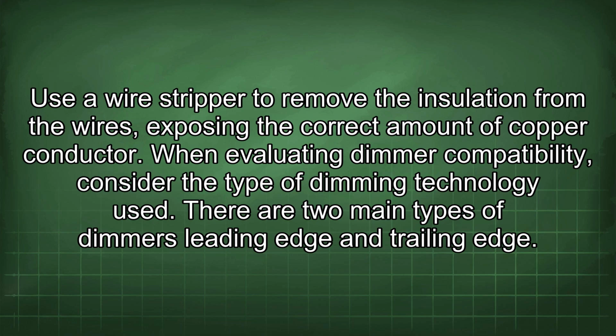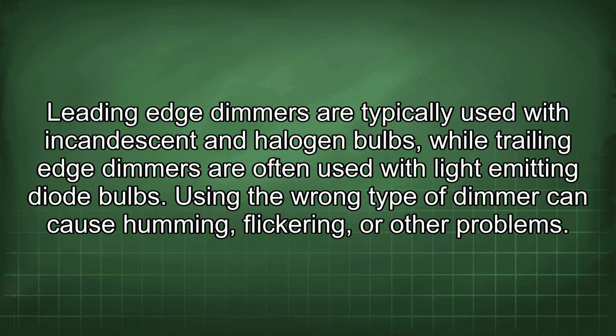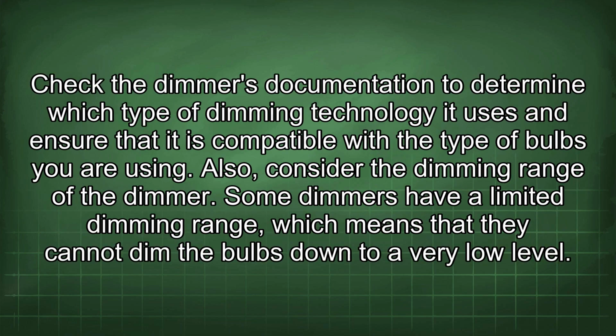When evaluating dimmer compatibility, consider the type of dimming technology used. There are two main types of dimmers: leading edge and trailing edge. Leading edge dimmers are typically used with incandescent and halogen bulbs, while trailing edge dimmers are often used with light-emitting diode bulbs. Using the wrong type of dimmer can cause humming, flickering, or other problems. Check the dimmer's documentation to determine which type of dimming technology it uses and ensure that it is compatible with the type of bulbs you are using.